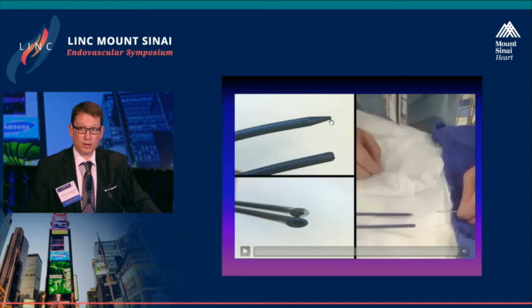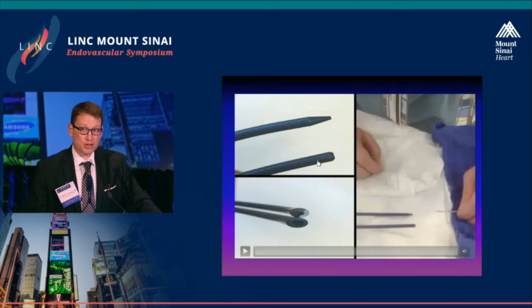The only difference in these two packets is this: one has a dilator that goes over the standard 038—this is the delivery one for just delivering a device—and you can see it has a much smaller internal diameter, whereas the exchange system can go all the way up to a 0.088 diameter. So the standard one, if you try to exchange, will not deliver a capture sheath.